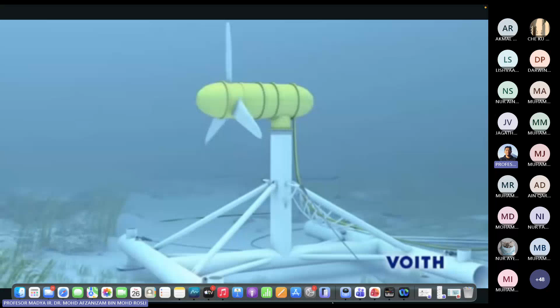Via the sea cable, the generated electricity is directly transmitted to an onshore inverter station, then fed to the grid via a transformer. This robust and simple subsea technology gives long intervals between maintenance, minimizing the use of extremely expensive marine equipment. When the turbine is due for maintenance, the facility is shut down and disconnected from the grid onshore.